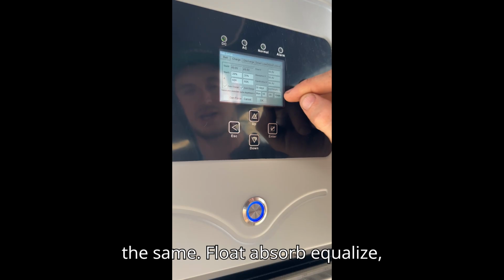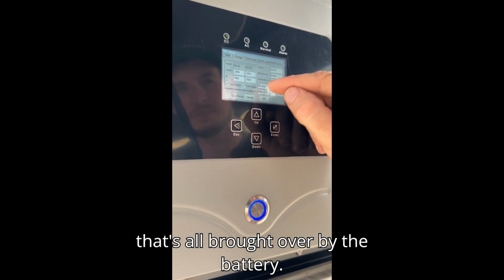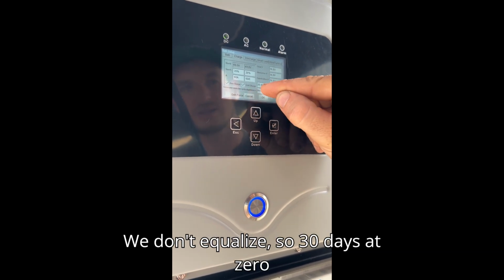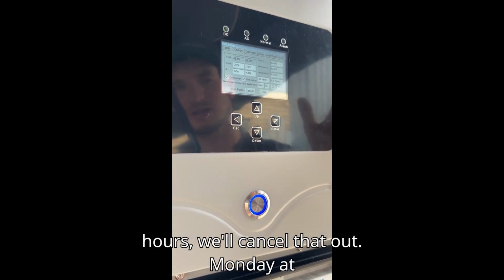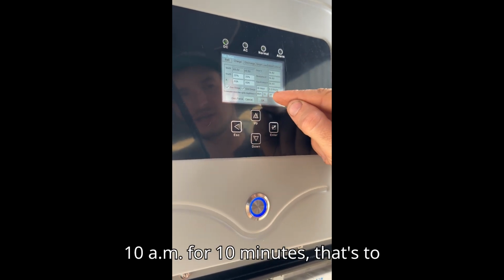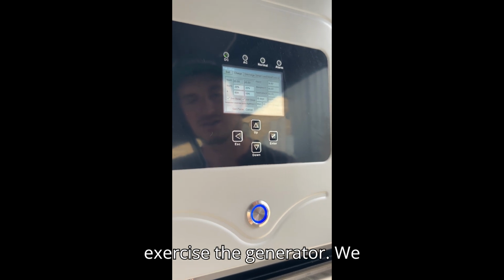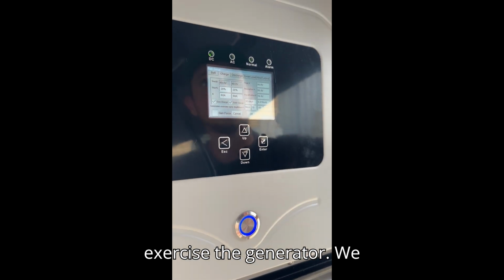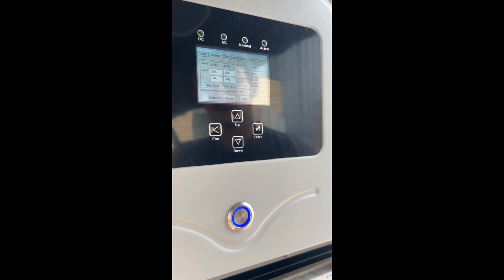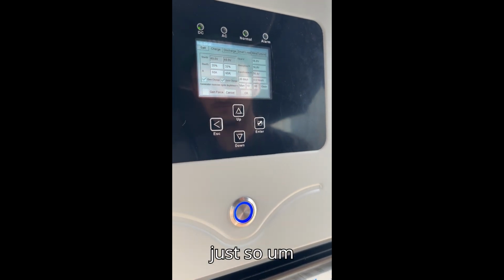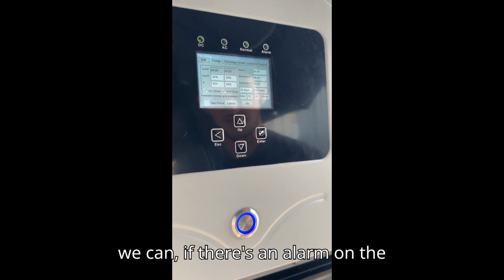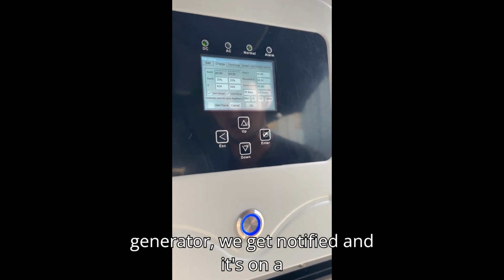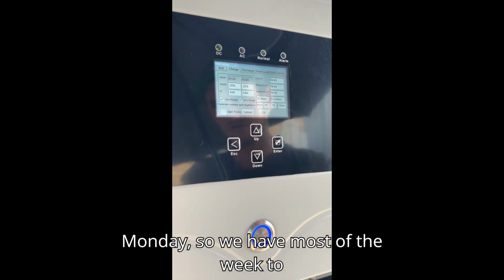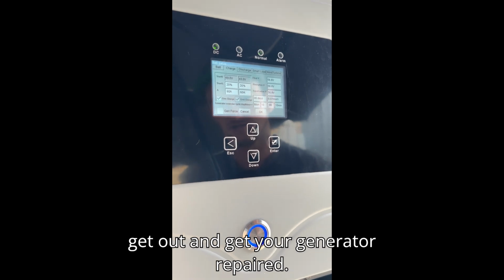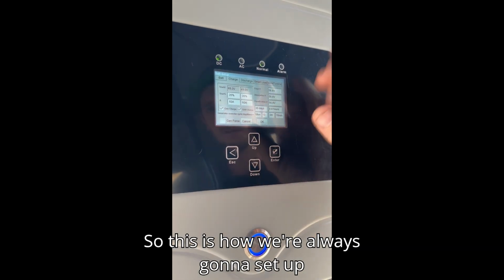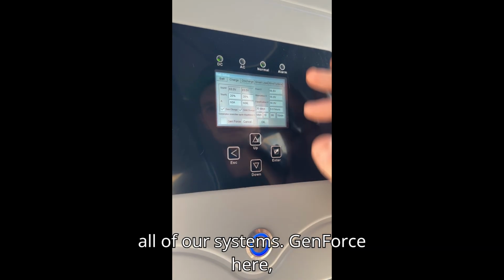Float, absorb, equalize, that's all brought over by the battery. We don't equalize, so 30 days at 0 hours, we'll cancel that out. Monday at 10 a.m. for 10 minutes, that's to exercise the generator. We always program ours that way so that if there's an alarm on the generator, we get notified, and it's on a Monday, so we have most of the week to get out and get your generator repaired. So this is how we're always going to set up all of our systems.